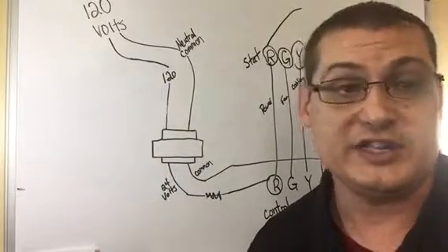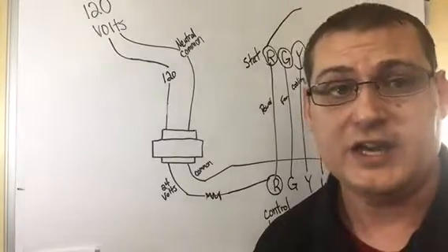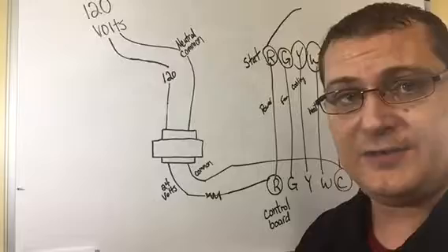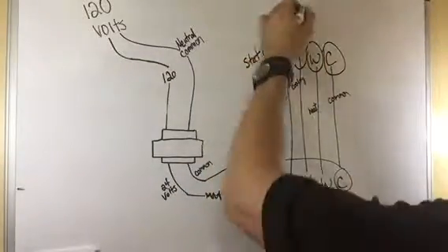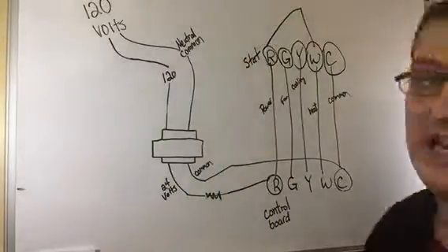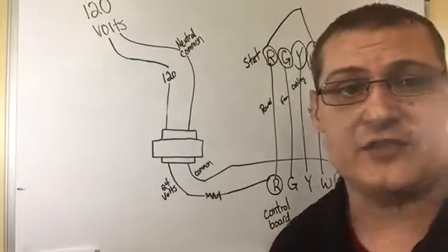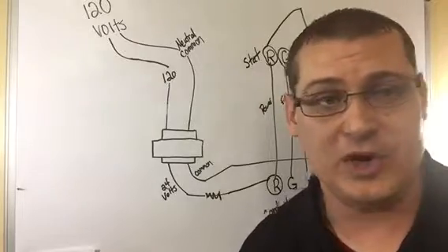Once you turn it up on a digital thermostat, you'll hear a click. Well, as soon as that click makes, it's just the relay inside the thermostat that is basically taking R and putting power to W. And then the control board does its thing from there. It starts the sequence of operation for the heat mode.